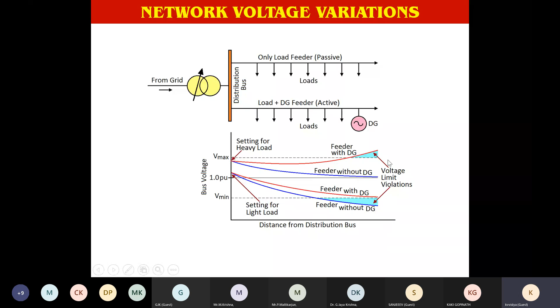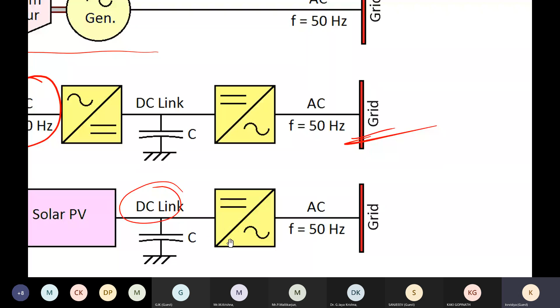Then comes the power quality issue because of the interfacing. Our typical thermal power plant or hydro power plant, we connect with the grid directly because these are all synchronous machines, 50 hertz machines. Whereas when you go for renewables like wind and solar PV, a wind turbine is a rotating machine and AC generator. But unfortunately, the frequency of the wind turbine generator is not 50. So we need a power electronic converter for converting that AC to DC, then DC back to 50 hertz, so that you can connect to the grid. Solar PV output is DC. In any case, we need the converter. So most of the renewables are grid connected through converters.